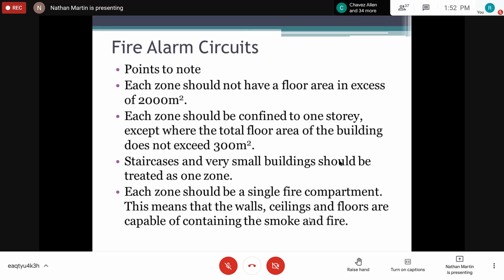Points to note about the fire alarm circuit. Each zone should not have a floor area in excess of 2,000 meters squared. Each zone should be confined to one story, meaning if it's a multi-story building, every floor should be considered a zone of protection, right? Except where the total floor area of the building does not exceed 300 meters. Staircases and very small buildings should be treated as one zone.